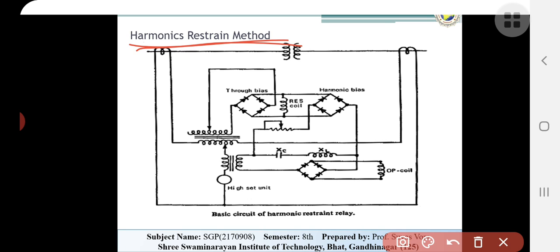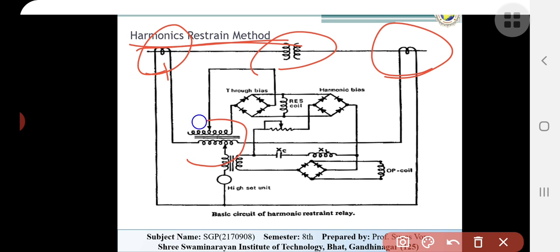Now in the diagram you can see the basic diagram. This relay provides the protection against the magnetizing inrush current. The initial primary, you can see, this one is the basic system. The primary winding current of the transformer on no load may be many times greater than the rated current. So you can see that this one is the input and this one is the output. Then these are the connections of the two different circuits with the transformers.